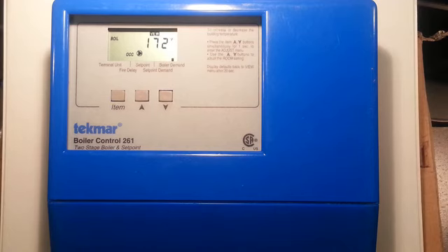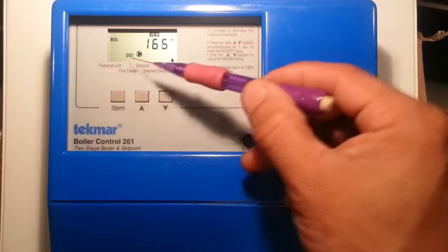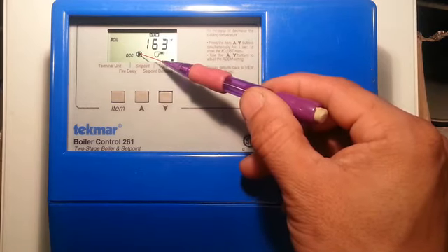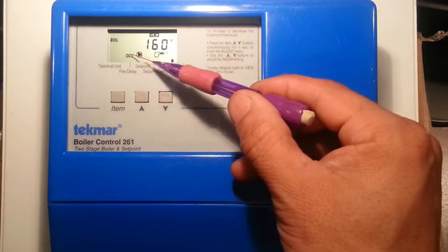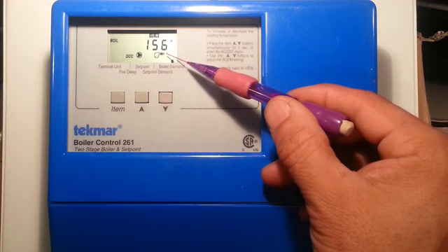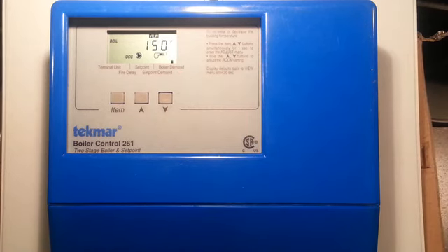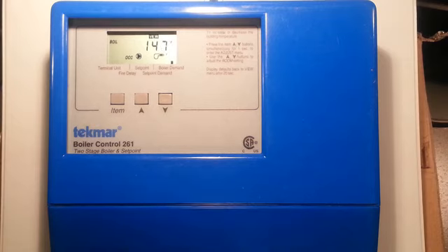If we quickly go through the icons on the display, you can see that the Tekmar control is currently showing a boiler demand. The boiler pump, system pump, is to be on right now. It's in occupied mode. It's just the temperature has dropped and it started looking for a first stage firing. If the temperature drops some more, you'll see it kick into second stage, and then obviously the boiler should have the corresponding second stage firing as well.